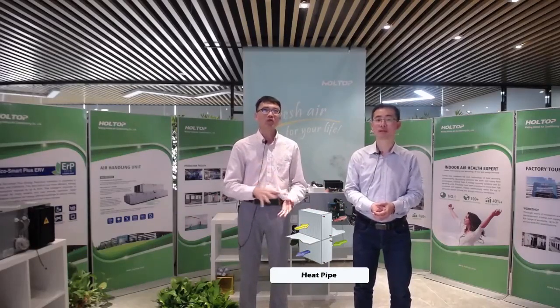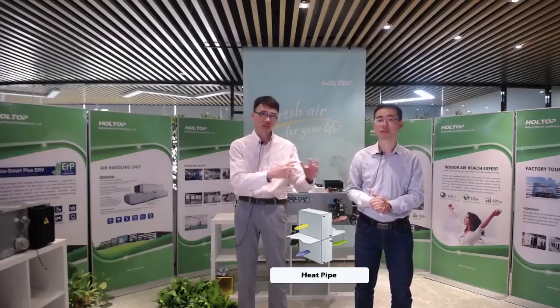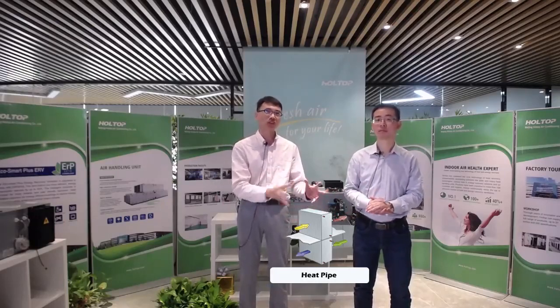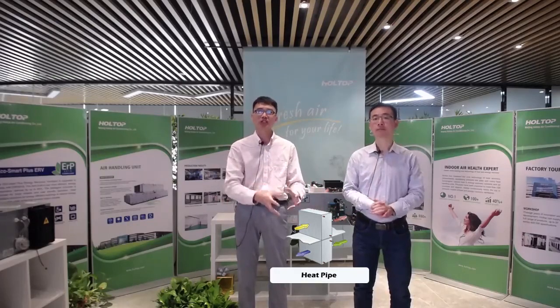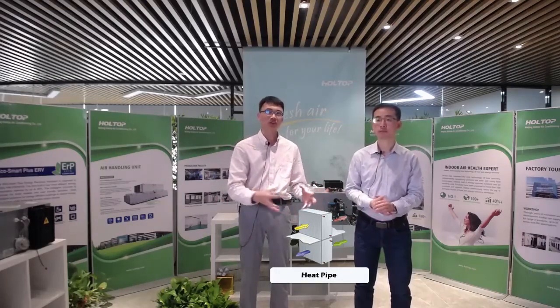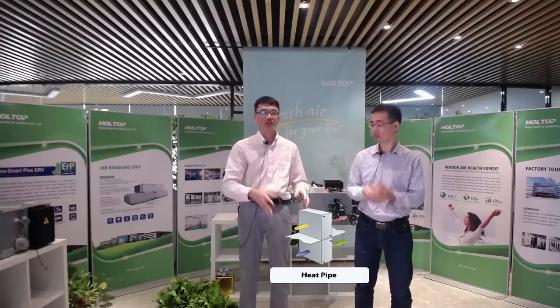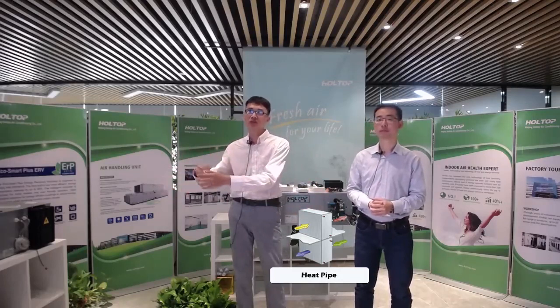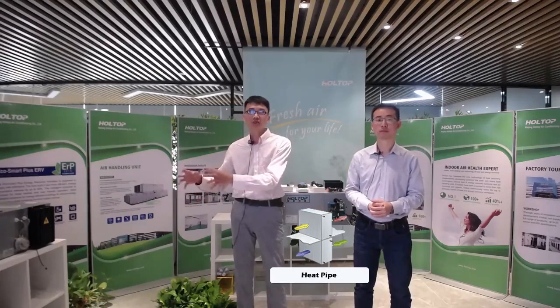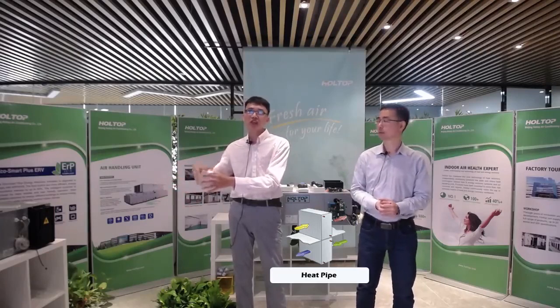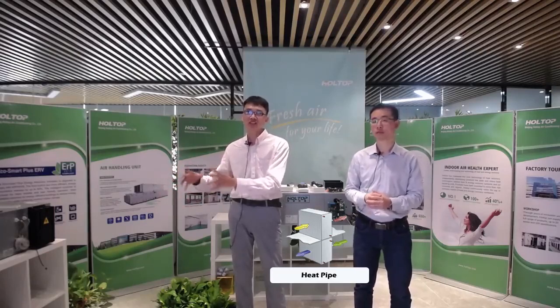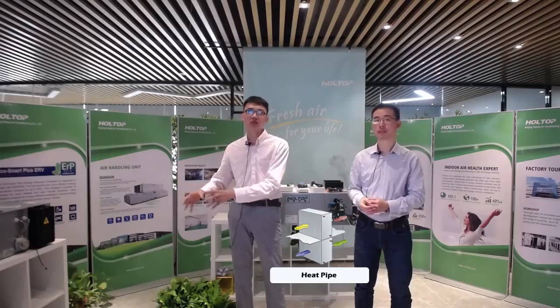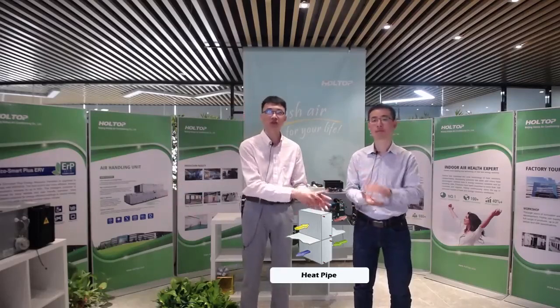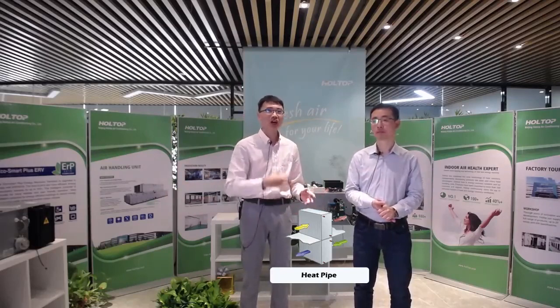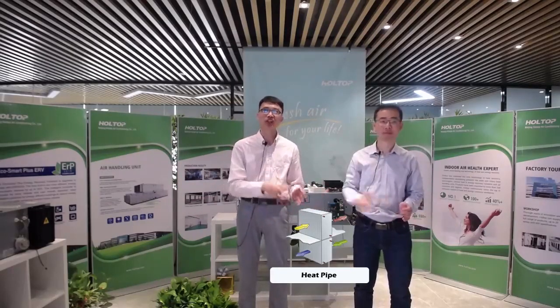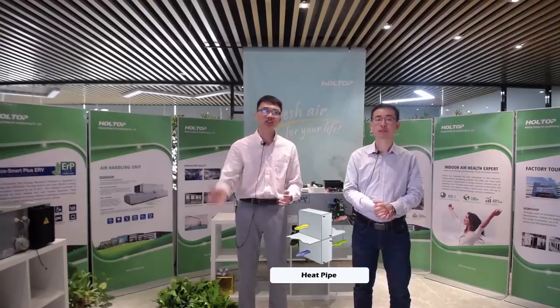When one end of the heat pipe is heating, the liquid refrigerant inside will absorb the heat and evaporate, and the steam flows to another end of the pipe by pressure difference. The steam will meet the cool air here and release heat and condense back into liquid. The liquid refrigerant will flow back to the evaporator end. So this is the circuit, how to play the heat recovery from high temperature ends to low temperature ends constantly.